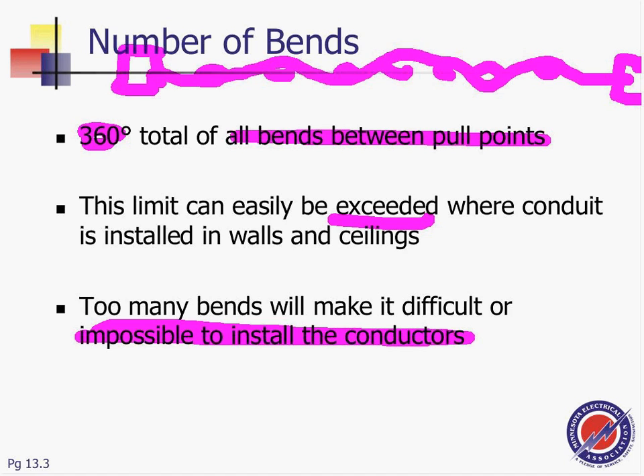I had a situation one time in a motel. I pulled a circuit, and because I was so lazy, I didn't want to use EMT, so I used flex. I'm probably 30 feet from a gear box, I think it's probably 20, 30 feet. Even though I have access to the cable in the suspended ceiling, so I can see it, it was really a pain trying to pull the conductors.